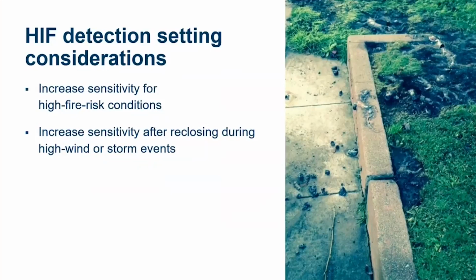Essentially the conductor would break, it would hit either the neutral or something else as it fell to the ground, and they would trip on that first fast curve. Then once it was on the ground, it was a high impedance fault and there wasn't enough current to trip any of the curves. So what they did was increase sensitivity for high impedance fault detection after that first reclose. While they were in cycle mode, they increased the sensitivity in some cases. There are many different ways that we can apply this. Those are just a few examples.